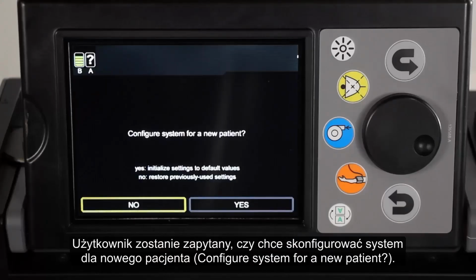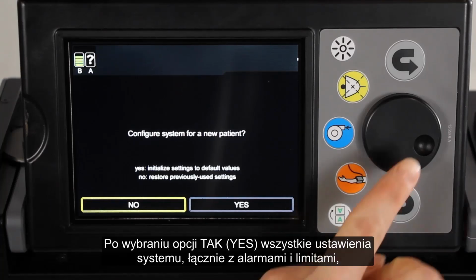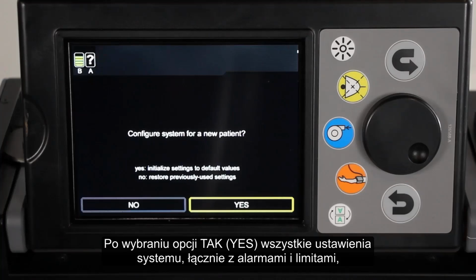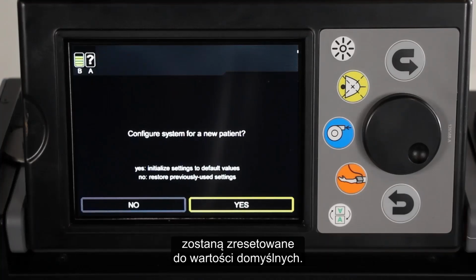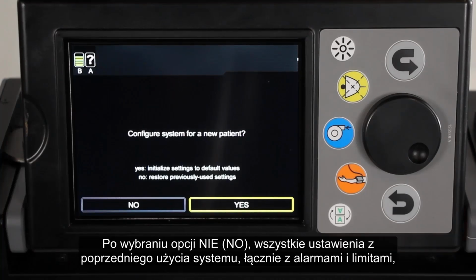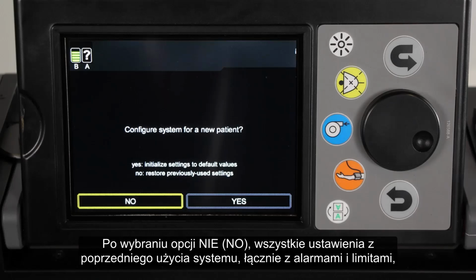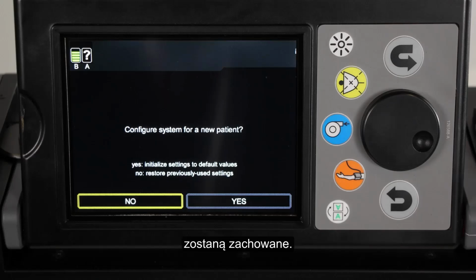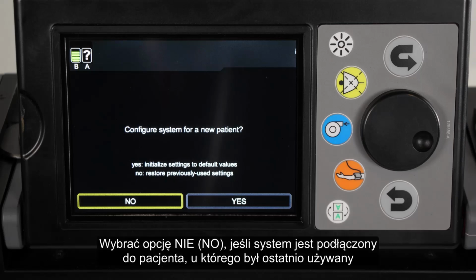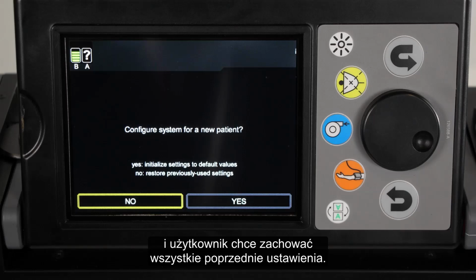screen will be displayed and will ask if the operator would like to configure the system for a new patient. If yes is selected, all system settings including alarms and limits are reset to their default values. If no is selected, all system settings including alarms and limits are retained from previous use. Select no if the system is connected to the patient on whom it was last used and you want to keep all the previous settings.